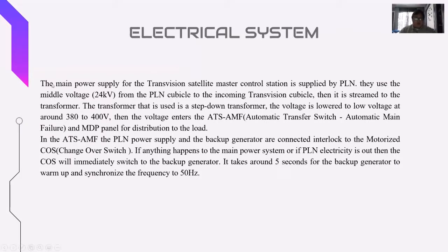The electrical system starts from the PLN, which is their main power supply. They use the middle voltage, which is 24 kilovolts, from the PLN cubicle into the Transvision cubicle. Then it is streamed to the transformer. The transformer that is used is a step-down transformer. The voltage is lowered to low voltage at 380 to 400 volts. Then the voltage enters the ATS AMF panel and then the MDP panel.